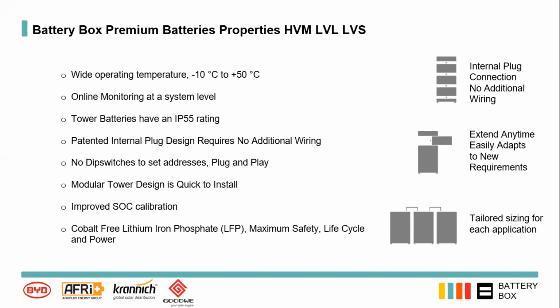We've also got improved SOC calibration, which allows for a much more accurate forecast of the available energy in the battery. And lastly, all our LFP batteries are cobalt-free, and that makes them a much greener battery, much safer for the environment. The batteries have been tested to the maximum safety standards, and they've got high life cycles and high power.